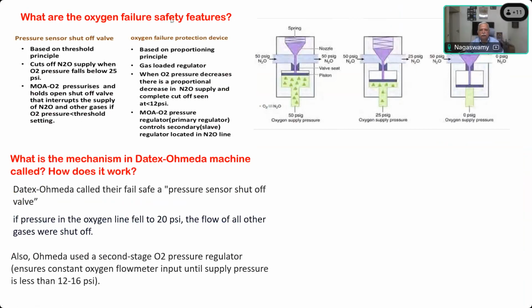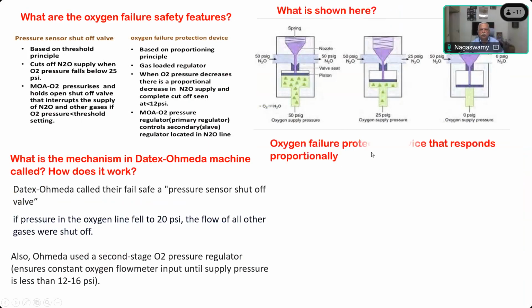When the oxygen supply pressure is 50 psi, it allows the nitrous oxide to go at 50 psi, and it reduces the nitrous pressure also to 25. When there is 0 psi oxygen supply pressure, nitrous oxide is totally cut off. So that's how the system works, an oxygen failure protection device that responds proportionally. What audible alarms are used and how do they work to indicate oxygen failure?